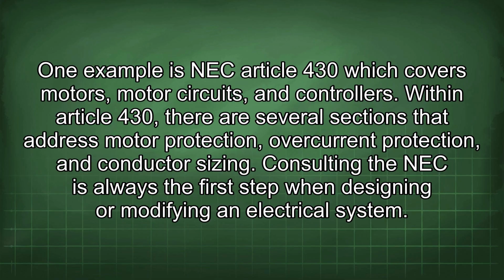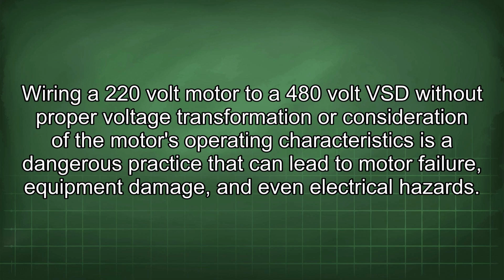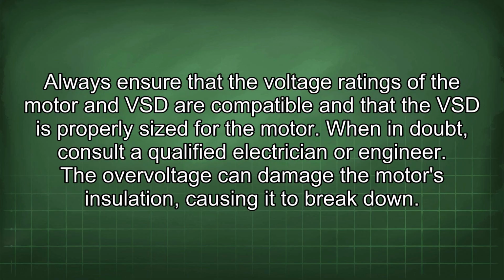Consulting the NEC is always the first step when designing or modifying an electrical system. Wiring a 220-volt motor to a 480-volt VSD without proper voltage transformation or consideration of the motor's operating characteristics is a dangerous practice that can lead to motor failure, equipment damage, and even electrical hazards. Always ensure that the voltage ratings of the motor and VSD are compatible and that the VSD is properly sized for the motor. When in doubt, consult a qualified electrician or engineer.